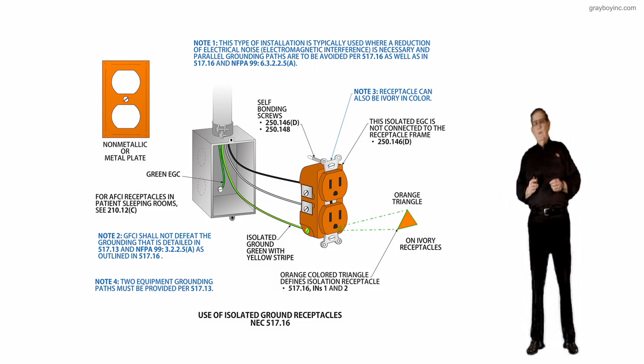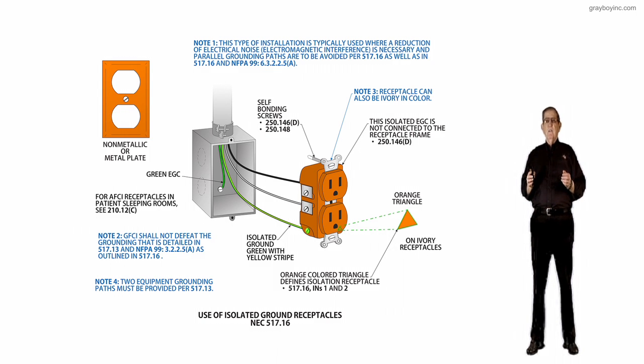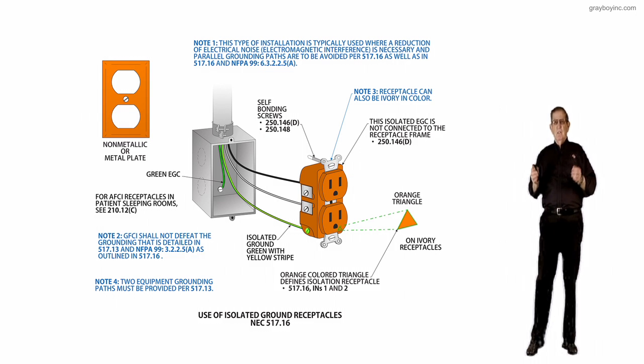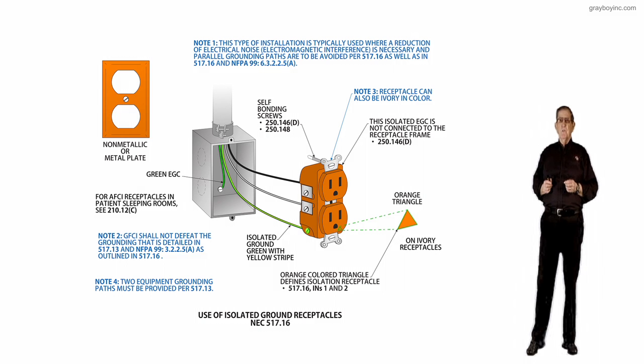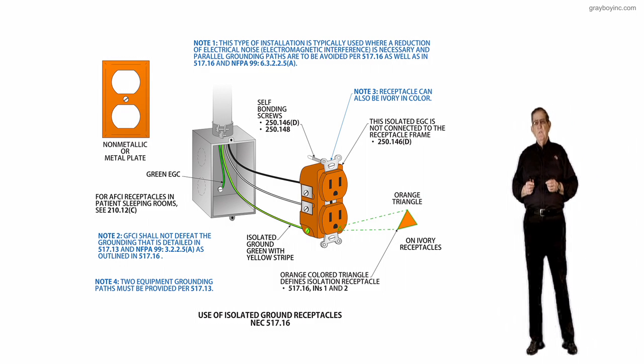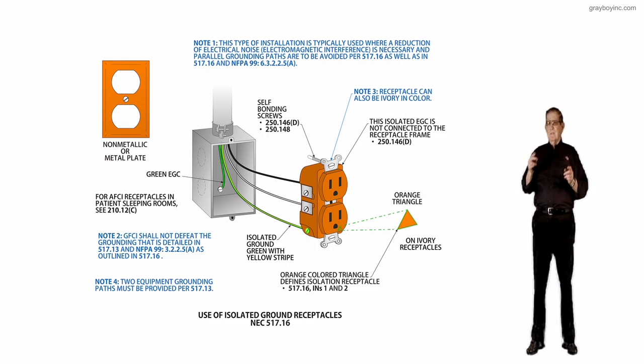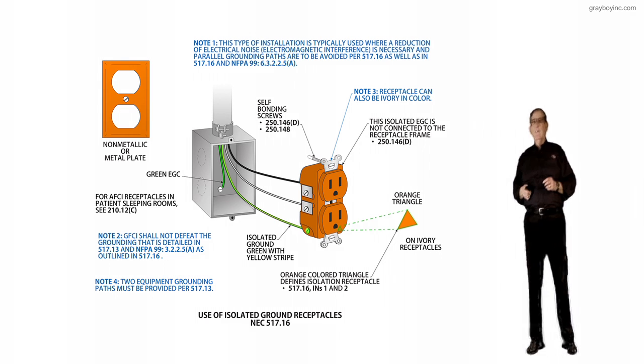Notice one thing: this receptacle is really not to be used in patient care areas because it doesn't provide the redundant grounding that's required by 517.13. Let's review the illustration and see what this new sentence is trying to point out.